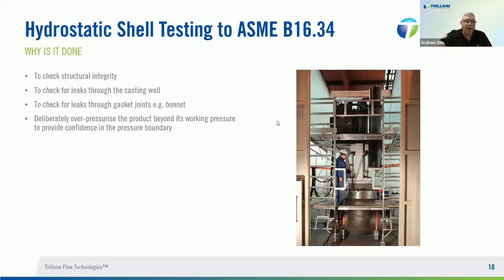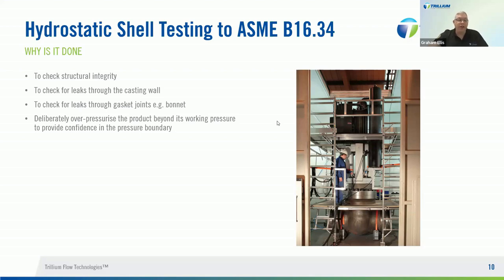Shell testing is done to ensure that we have a structurally integral valve: to check for leaks through the casting wall, to check for leaks through gasket joints such as body-bonnet joints, and by deliberately over-pressurizing the product beyond its working pressure to provide confidence in the pressure boundary of the valve.